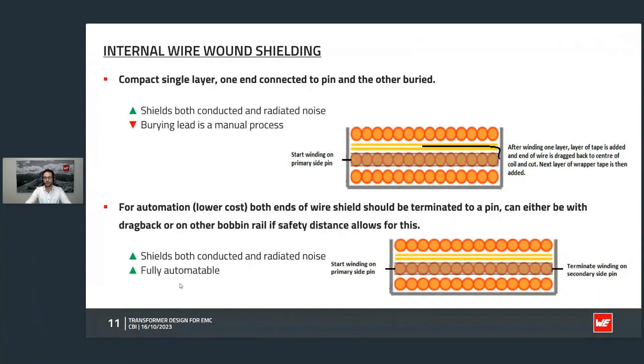You might ask: if it is so easy and can be done automatically, why do we not put it on every transformer? The answer is simple — even though it can be done automatically, the shield will still occupy space inside the winding window. In this schematic we exaggerated it a bit, but you see the shield takes about one third of the available winding space. Everyone tries to optimize their power supply for the best efficiency and every percentage point counts, so we want to use all available winding space for the actual windings carrying the current — the primary and secondary. So if not absolutely needed we would try to skip the shield winding, and we only put it if the customer really requires it, maybe because they have already seen EMI issues.